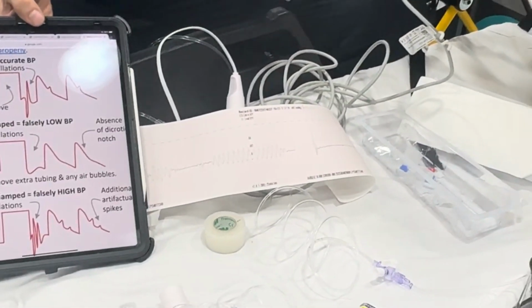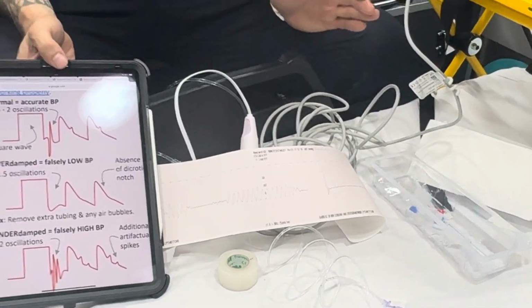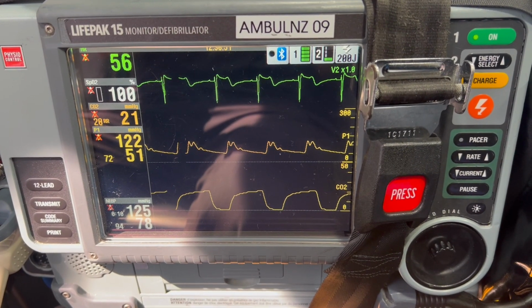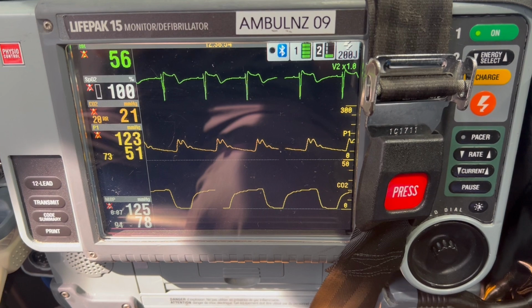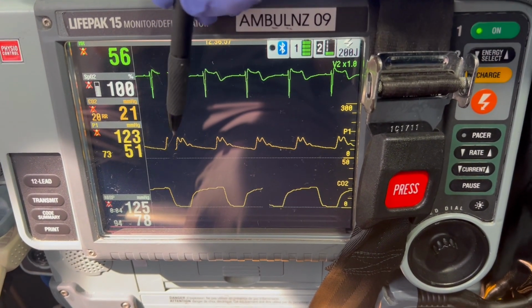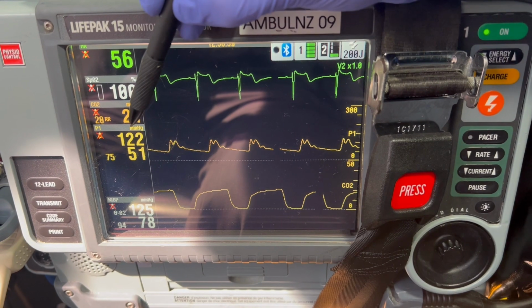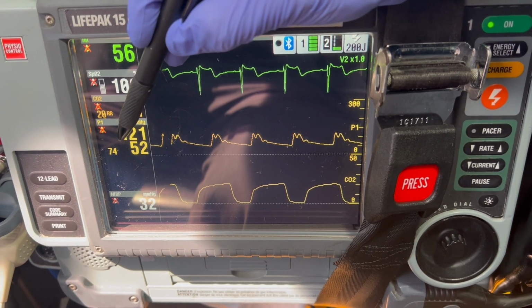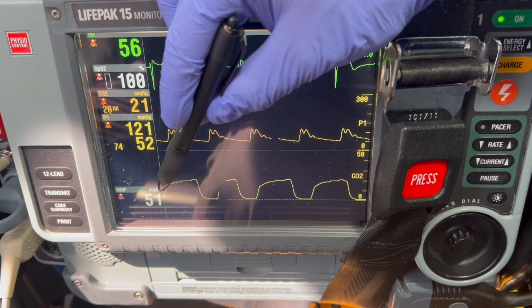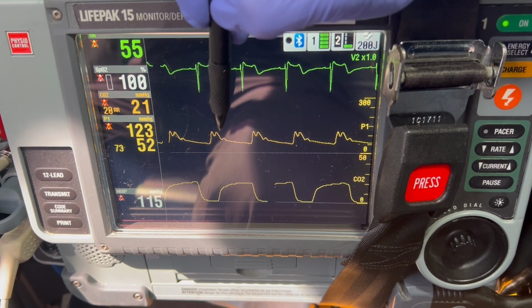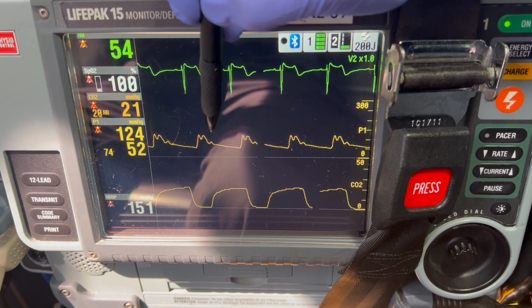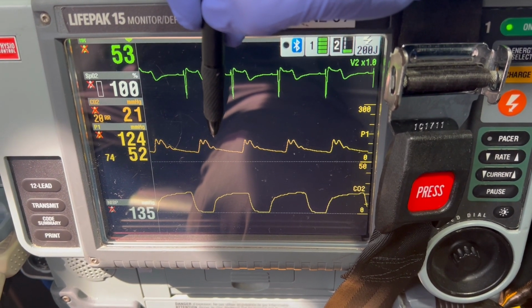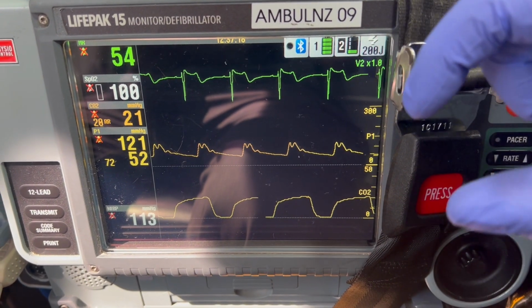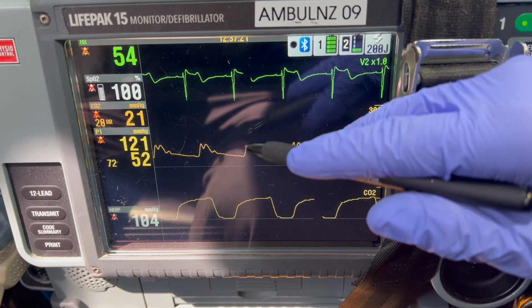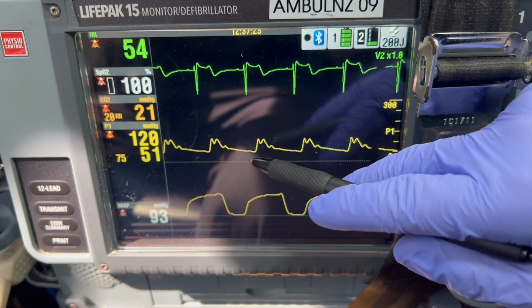I'm going to put in a video clip that I have on a real patient, so you see exactly how it's done and how it looks. This patient is on an arterial line, so invasive monitoring. He has a radial A-line. You see here we have the dicrotic notch. His BP is currently 122/51, 75 on the MAP, and here we have the non-invasive cuff going. I'm going to show you how to do a fast flush test, and you need that to know if you're properly damped. The way you do this, you basically find the pigtail or two press buttons on the transducer, quickly flush it, and let go. So you're basically flushing his A-line with saline. What you should see is oscillation, like movement up and down.